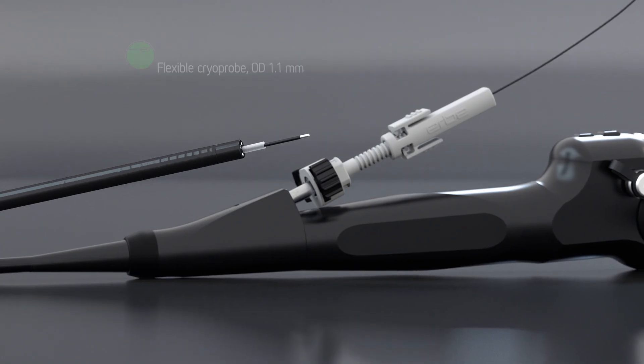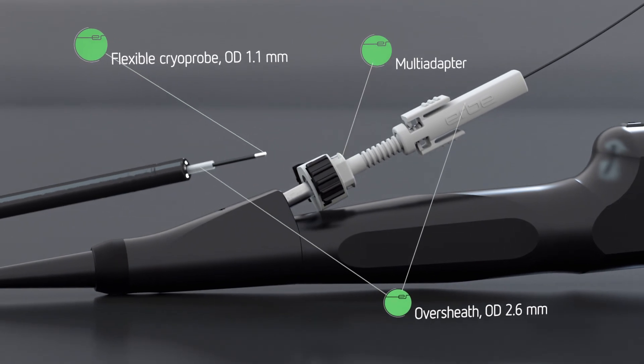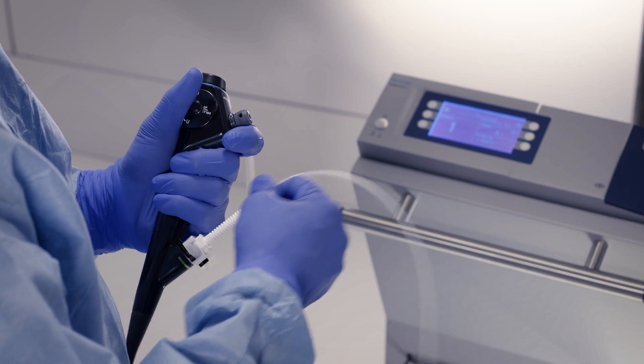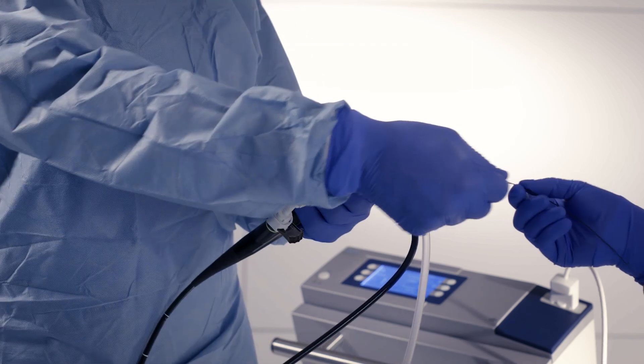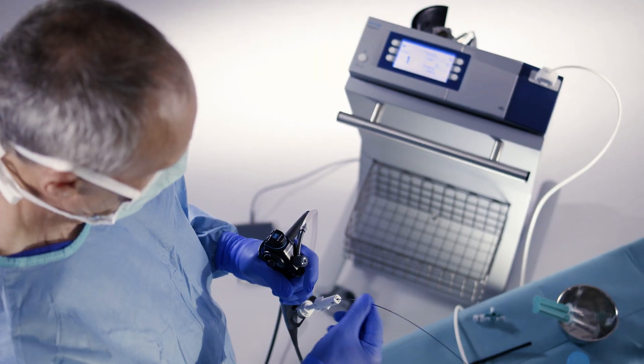The 1.1 mm cryoprobe with oversheath is our latest product development. The oversheath is inserted into the working channel of a standard bronchoscope via the multi-adapter. Then the flexible cryoprobe is inserted until it becomes visible in the endoscope image.